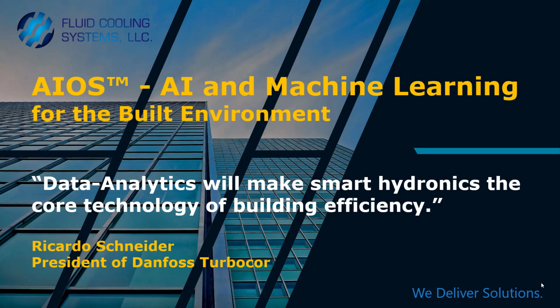There is a very exciting convergence taking place, and fluid cooling systems will be right there with equipment to make it work. That being machine learning and AI. What's taking place is that sensors are being installed all through a facility and through the chiller plants, the chill water set points, the condenser, the tower, the outdoor temperatures, the air handling. Everything that's taking place is being fed to sensors and then fed to basically large servers that's being stored in very small increments. And then AI takes over and looks at all of the different settings, all of the results of those settings, and makes informed choices that get better and better over time.